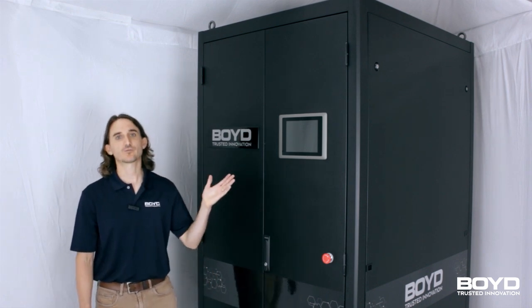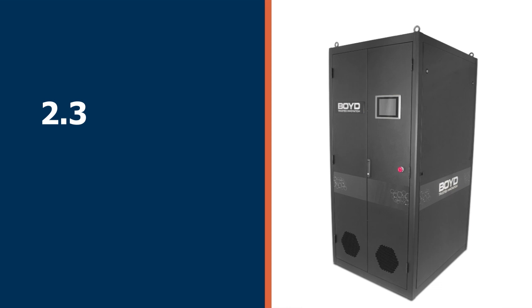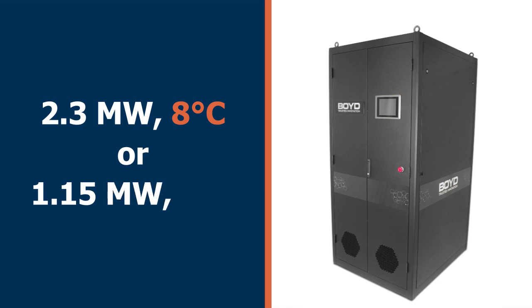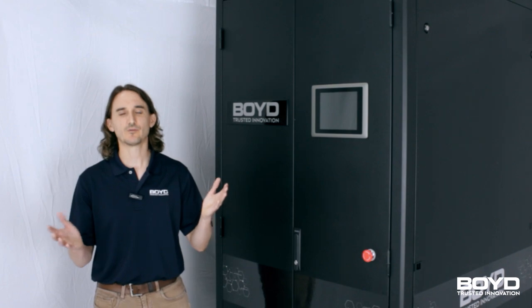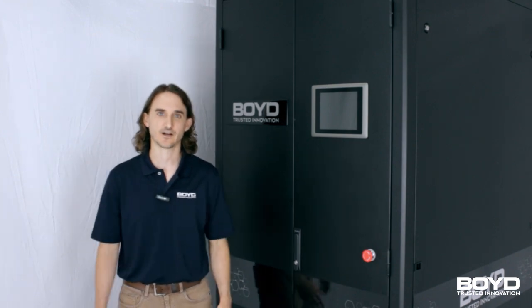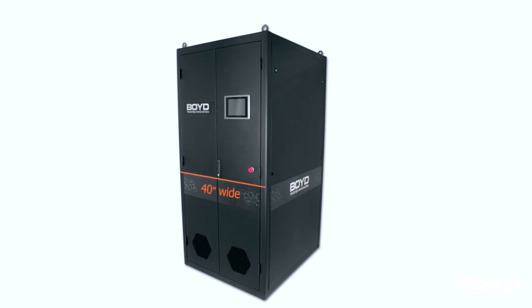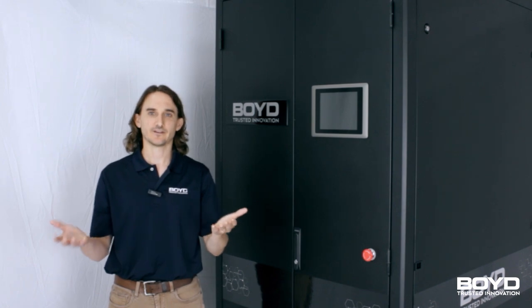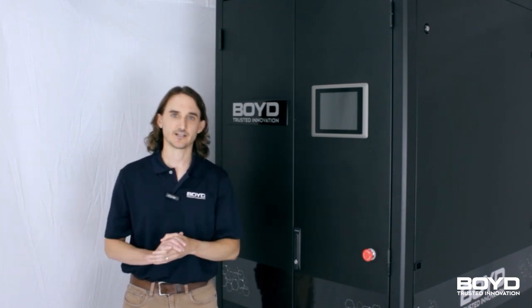This innovative new product can do 2.3 megawatts at an 8 degrees C approach temperature, or 1.15 megawatts at a 4 degrees C approach temperature. All this is capable in a very small, compact design, 40 inches wide, 48 inches deep, and 84 inches tall. This will enable it to fit in a very compact space in your data center.